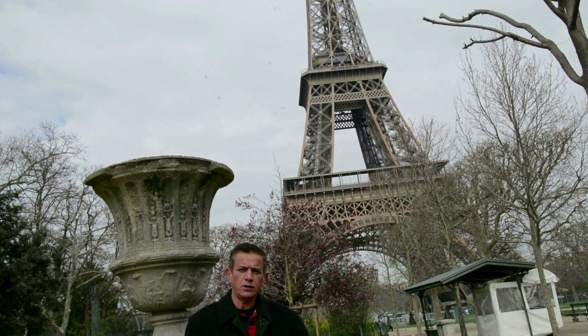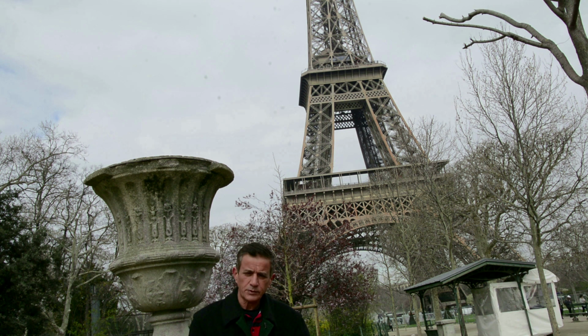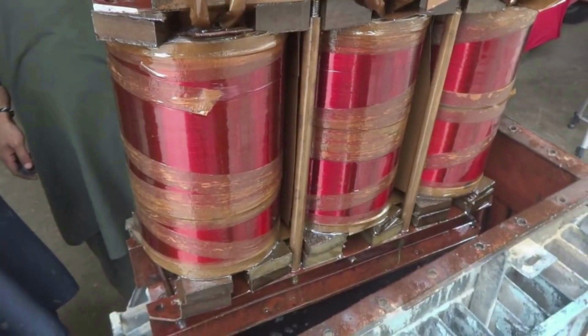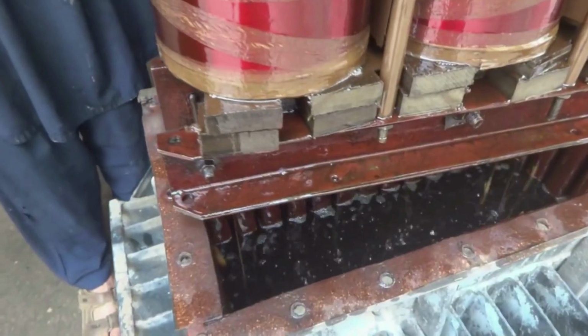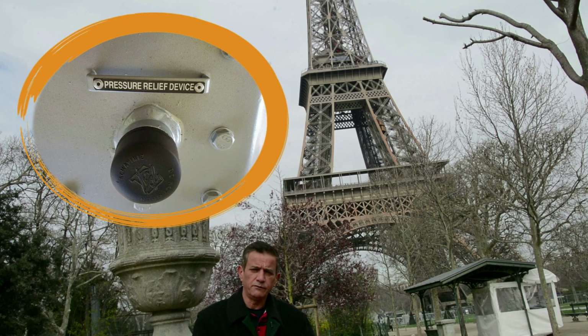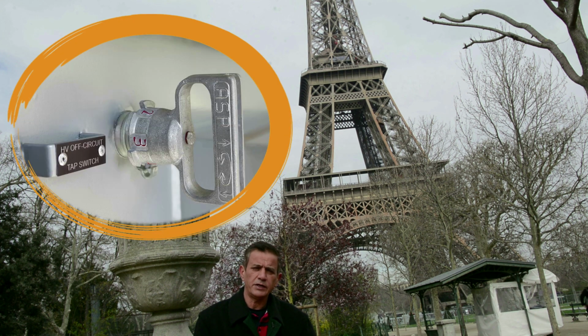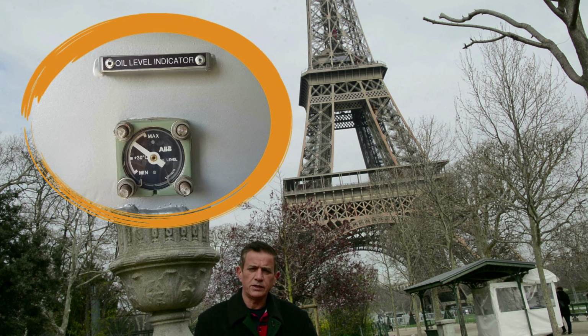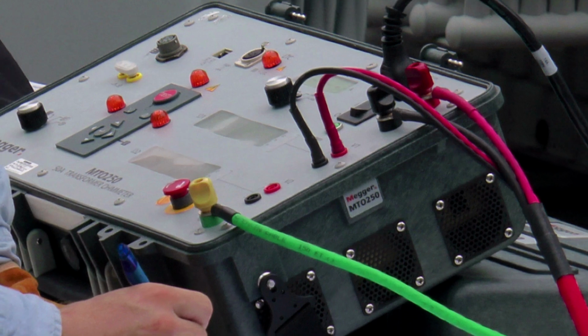These tests will take care of most of the transformer parts, and with the special tests, each single component of the transformer can be tested. Transformer has two major parts, as we said: active parts and passive parts. Active parts are the winding and the core. Passive parts are the tank, the oil, the pressure relief valve, the tap changer, oil level indicator, thermometer, etc.